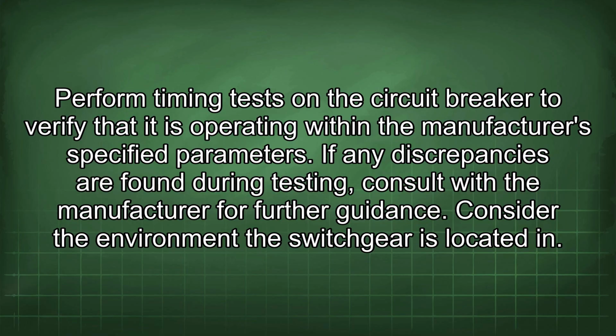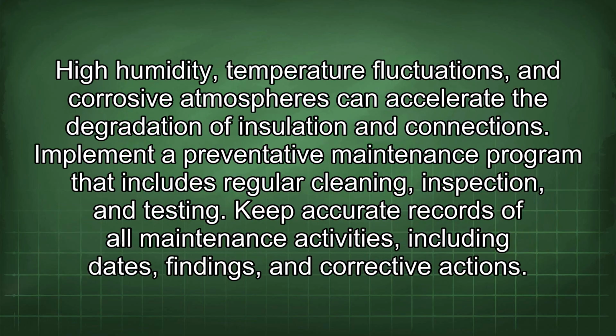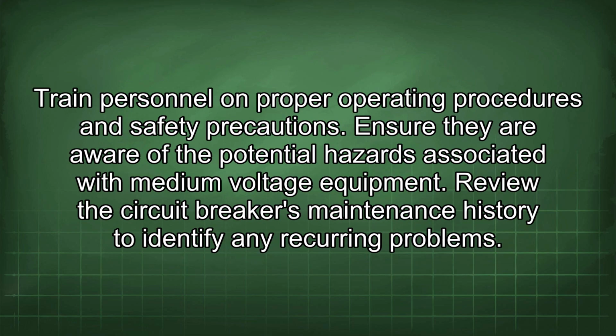Consider the environment the switchgear is located in. High humidity, temperature fluctuations, and corrosive atmospheres can accelerate the degradation of insulation and connections. Implement a preventative maintenance program that includes regular cleaning, inspection, and testing. Keep accurate records of all maintenance activities, including dates, findings, and corrective actions. Train personnel on proper operating procedures and safety precautions. Ensure they are aware of the potential hazards associated with medium voltage equipment.